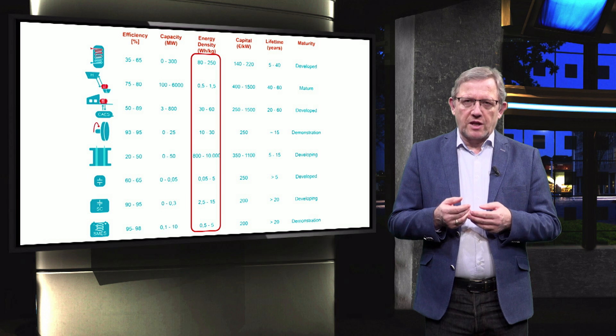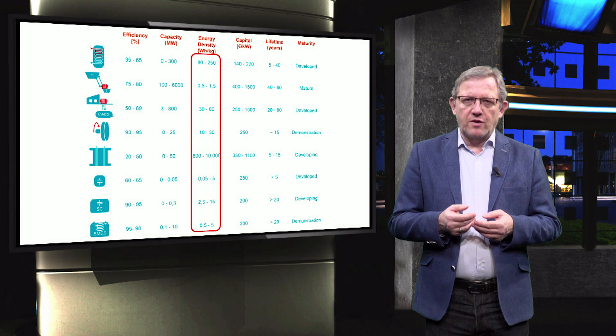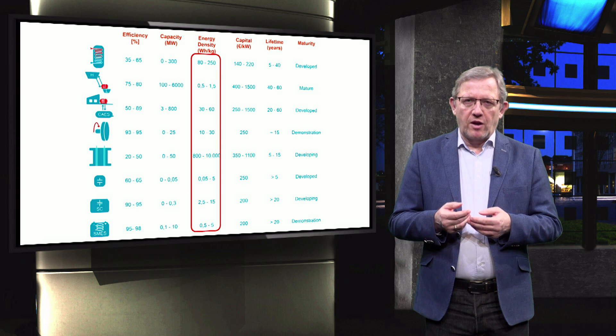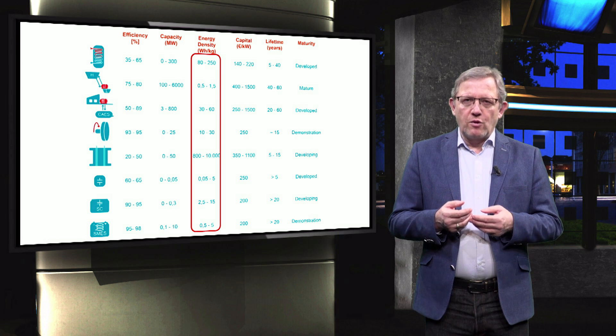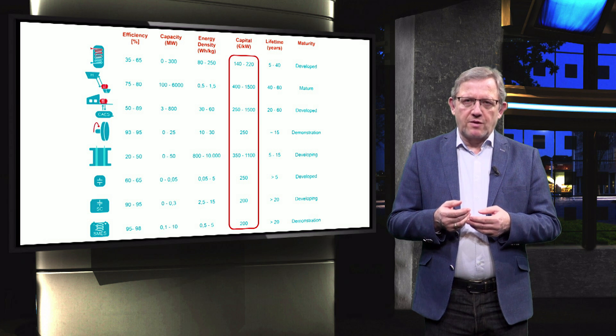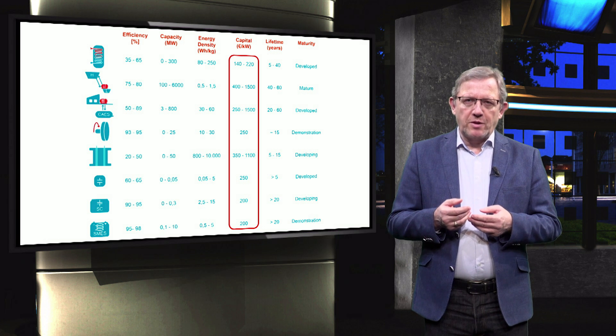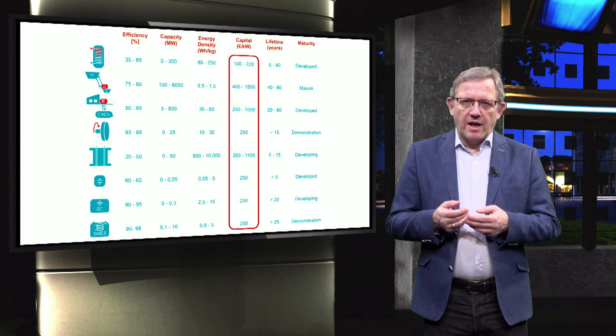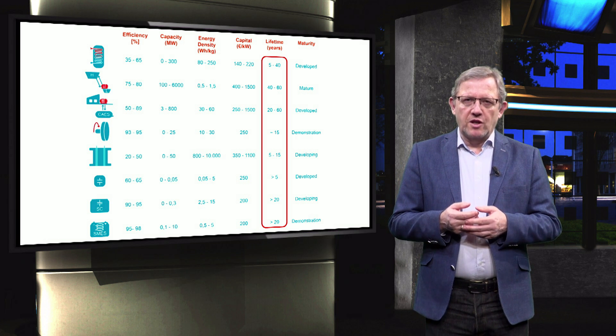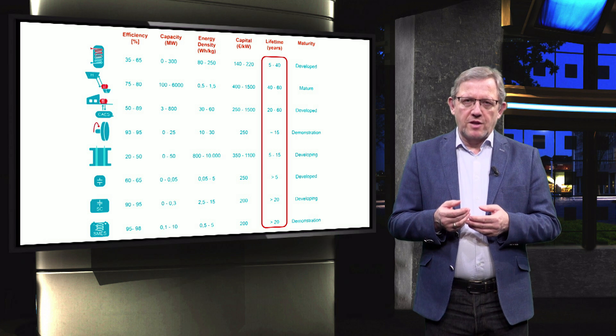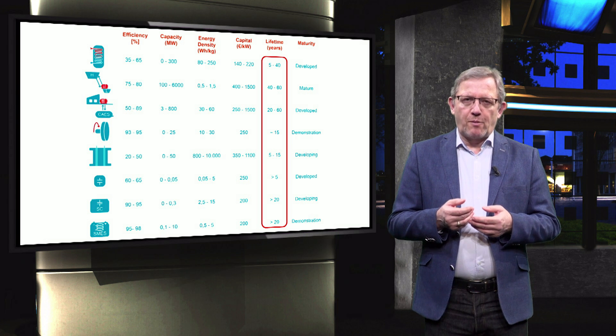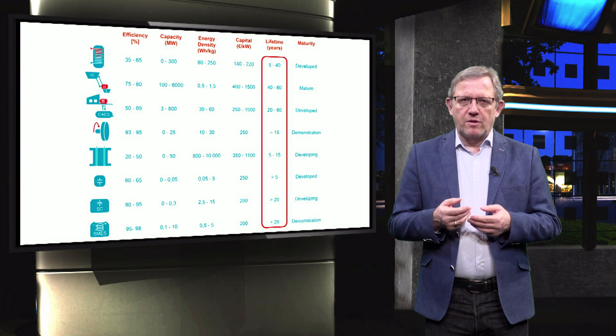Most energy storage technologies except thermal storage, fuel cell and batteries would have a low energy density. Fuel cell is one of the most expensive storage technologies with high capital cost. Pumped hydro and compressed air energy storage have the highest lifetime, up to 60 years, while capacitors have the lifetime around 5 years.